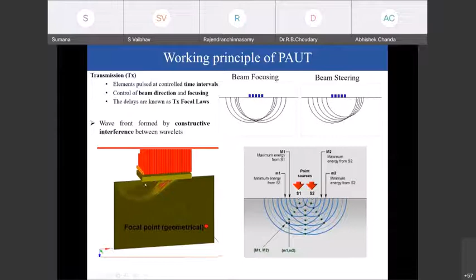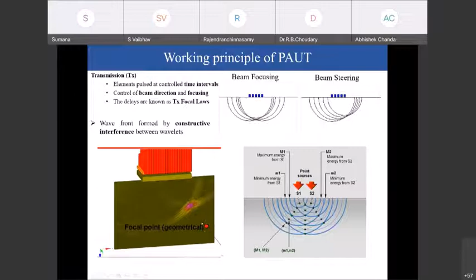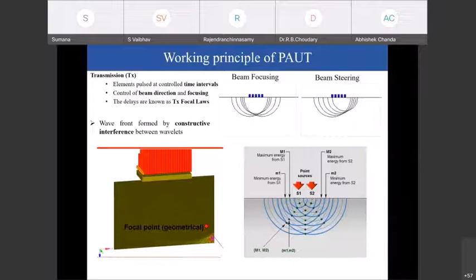Like if you see here in the beam focusing animation, the start and last elements are first transmitted, and the middle one is later transmitted, so that you will get a desired position, the focused beam. In case of beam steering, a linear delay is applied. So in this animation, you can see the first transmission is done by the first element, and then the last element, so that at the focal point, all the elements will be in phase at this position.